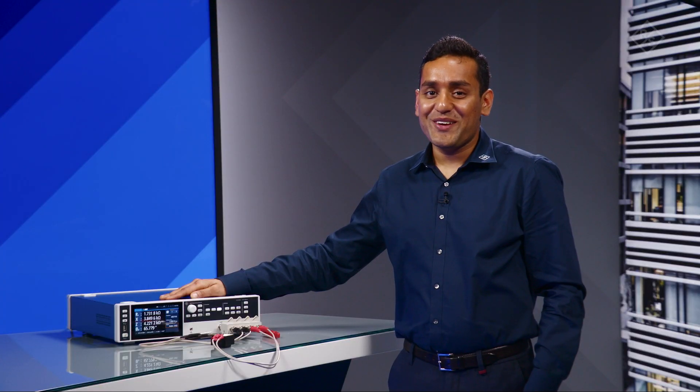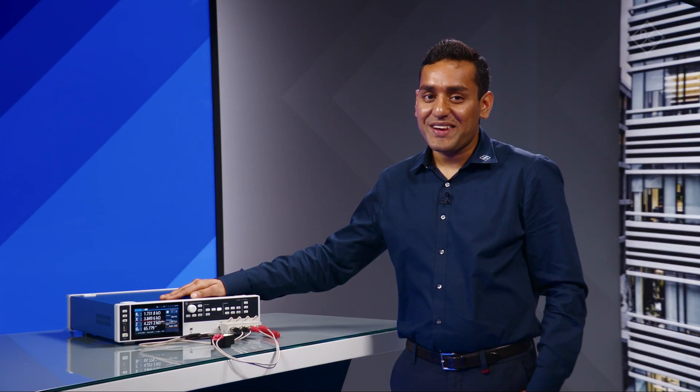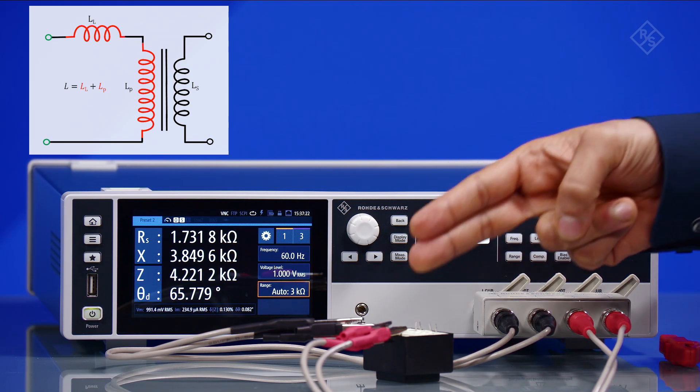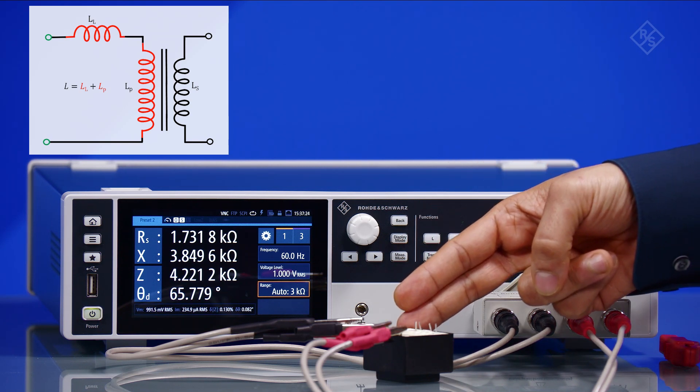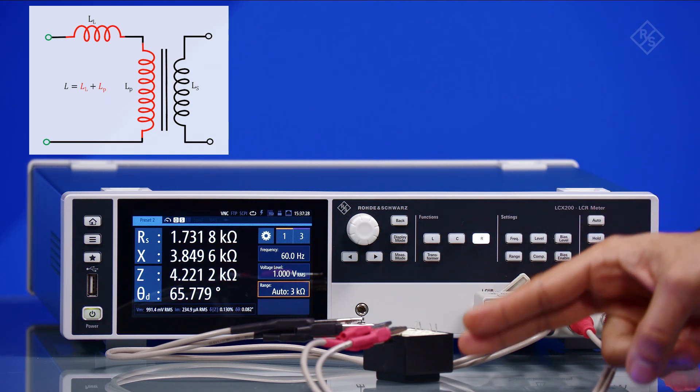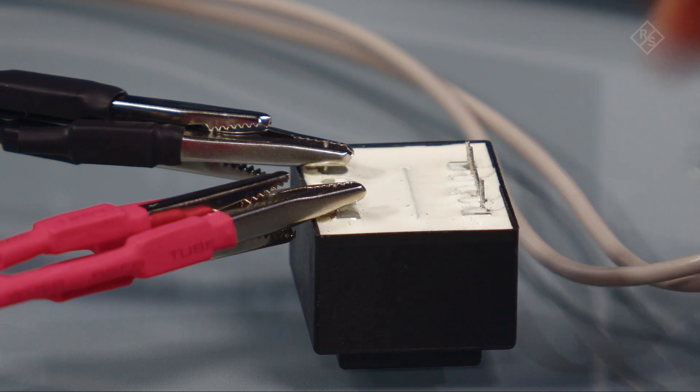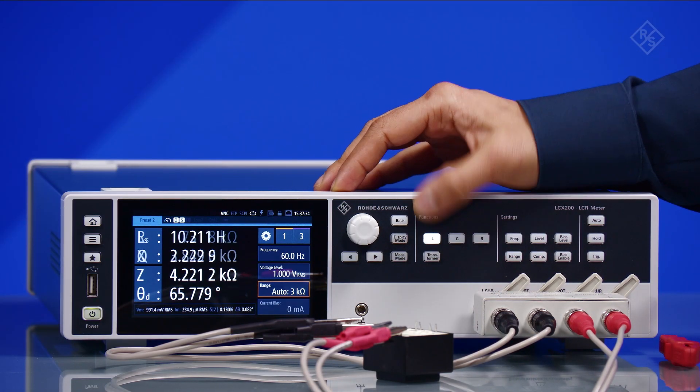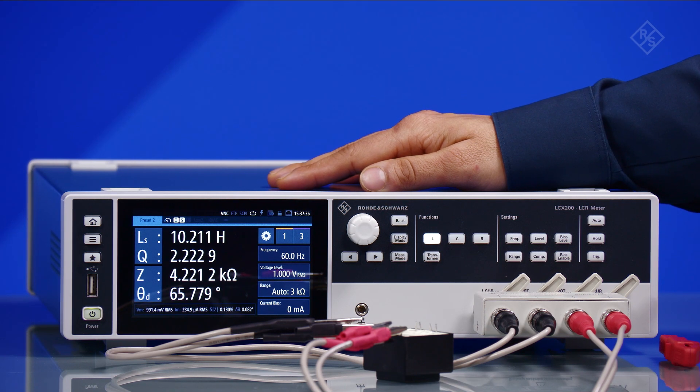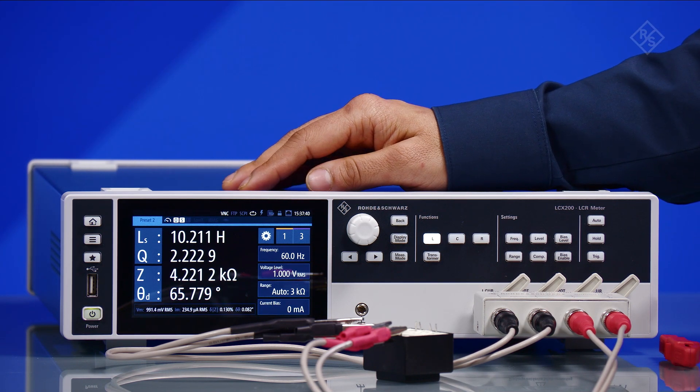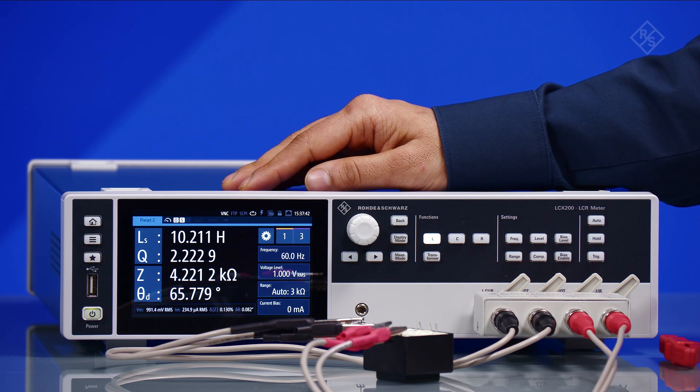In order to measure primary inductance, please connect the common test leads to one terminal of the primary winding, and connect the one and N test leads to the other terminal of the primary winding. Leave the secondary winding open and press the L key. The high resolution screen of the LCX now displays the primary inductance of this transformer.